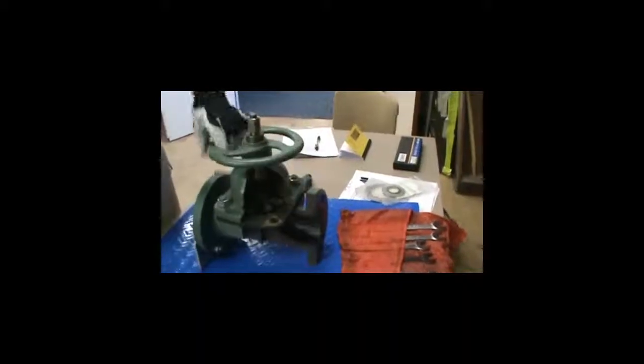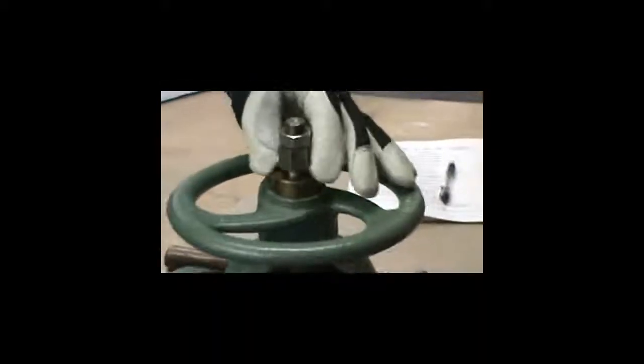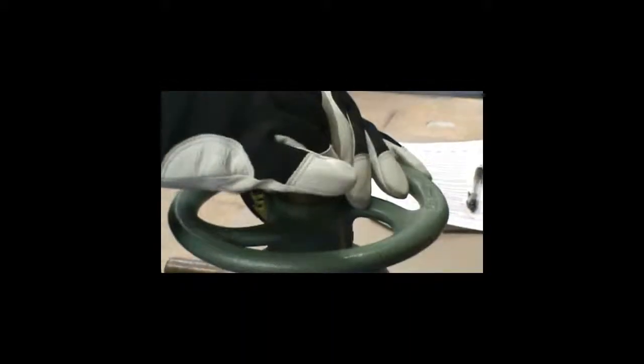One of the other major things on this valve that you see these two nuts up here, one is a jam nut, one is an adjustment. This will set the stroke of the valve. This is very important.